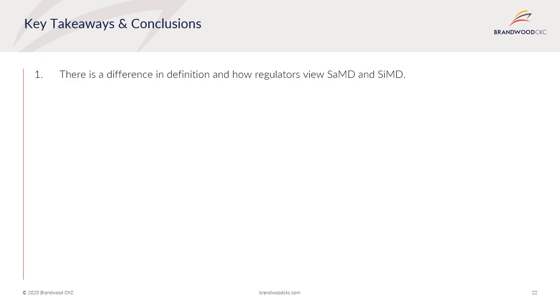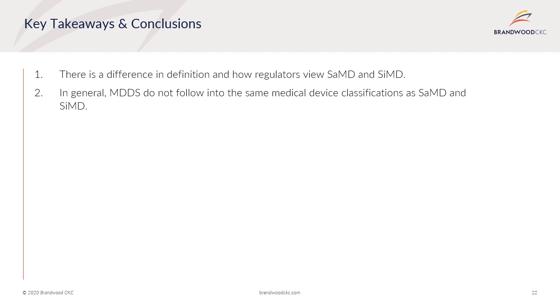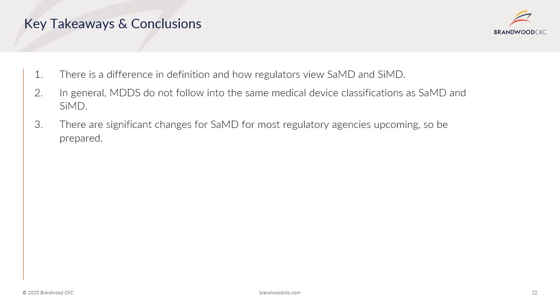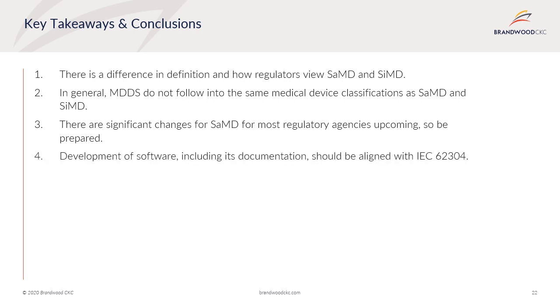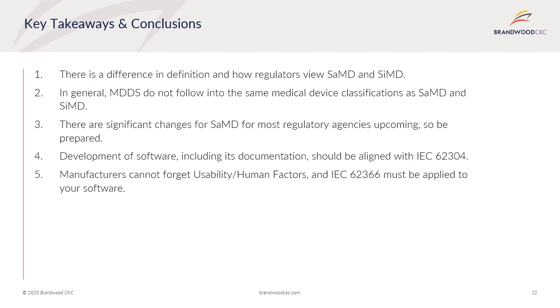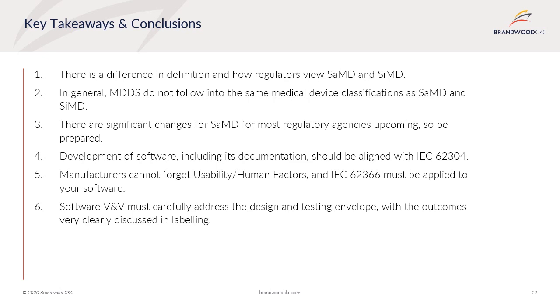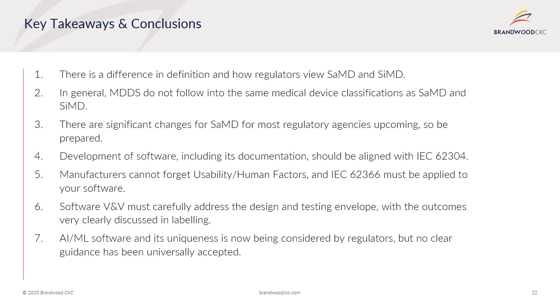To finish off this webinar, here are the key takeaways. Firstly, there is a difference in how regulators view software as a medical device and software in a medical device. In general, MDDS do not fall into the same medical device classifications as SAMD and software in a medical device. There are significant changes for software as a medical device for most regulatory agencies upcoming, so be prepared. Developmental software, including its documentation, should be aligned with IEC 62304. Manufacturers cannot forget usability and human factors — IEC 62366 must be applied. Software V&V must carefully address the design and testing envelope with outcomes clearly discussed in labeling. Finally, AI/ML software and its uniqueness is now being considered by regulators, but no clear guidance has been universally accepted.